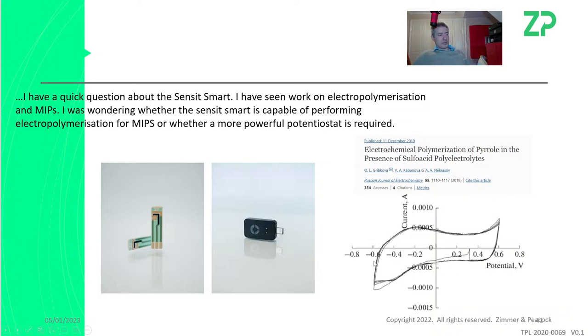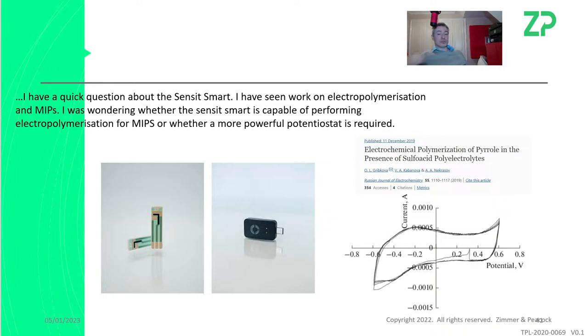I grabbed a paper from the literature to check what voltages they were using. I think the Sensit Smart could handle that working electrode voltage, but the user's concern is about compliance voltage. Honestly, we have not used the Sensit Smart to do electropolymerizations. I recognize the question — I think you stand a chance — but unless I've done it, I can't absolutely say yes. I feel the Sensit Smart is really an analytical tool, and what you probably need for synthesis is a more powerful potentiostat, so you can do both synthesis and analysis.